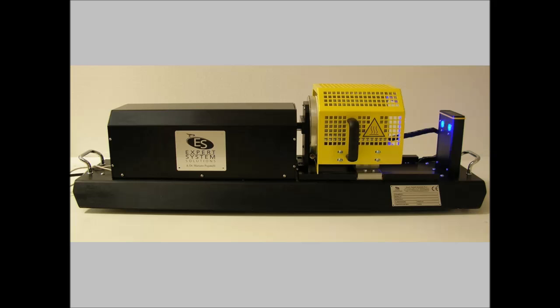The resolution of the horizontal optical dilatometer is 5 times higher than the vertical model HD, because it uses a sample 50 mm long, and the resolution of the optical system is pushed up to the limit of 0.5 micron, thanks to the use of a light source with a wavelength of 478 nanometers. Misura LT is the only dilatometer which can easily and hassle-free carry out high-resolution measurements on very thin materials, or on incoherent materials, or on plastic materials which cannot be touched during the test.